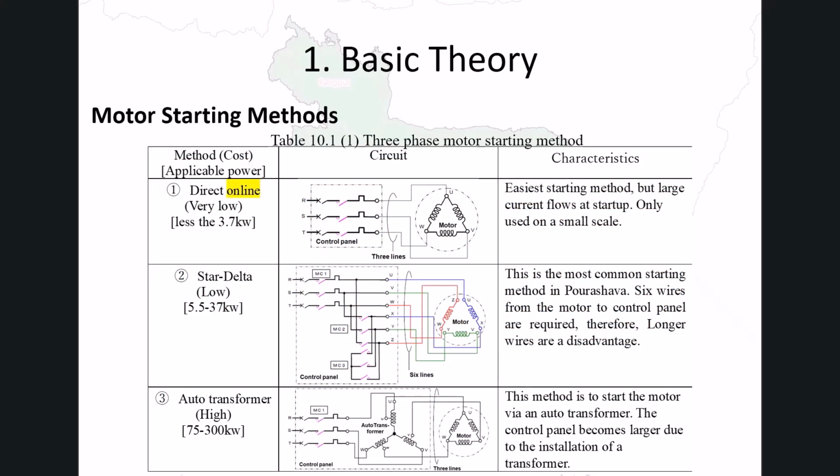When starting a motor, it accelerates until the rotational speed stabilizes, requiring high torque and causing large currents. Various starting methods exist to avoid the large current. This table compares the main starting methods of three-phase induction motors and their characteristics, providing a reference for selecting an appropriate starting method according to the motor capacity and installation conditions.